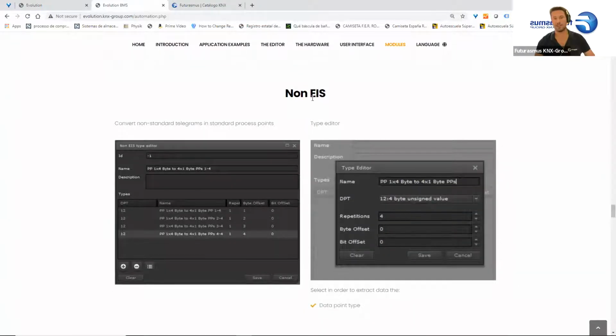Then you've got non-EIS. The word EIS is a little bit not up to date anymore. EIB interworking standard. Now it's called data point types. This is a module which transforms non-standard data point types into standard data point types. For instance, let's say you've got a weather station which sends a 14-byte telegram, and every 2 bytes it sends the different values for, let's say, the temperature value, the illumination, the azimuth, the elevation, the whatever, and it's coded in 2 bytes, 2 bytes, 2 bytes, 2 bytes, and you want to uncode this information. You just set up here 14 bytes, and you set up the repetitions, the byte offset, the bit offset, and then it will generate automatically the process points for you, and you can use those standard process points now in the project.